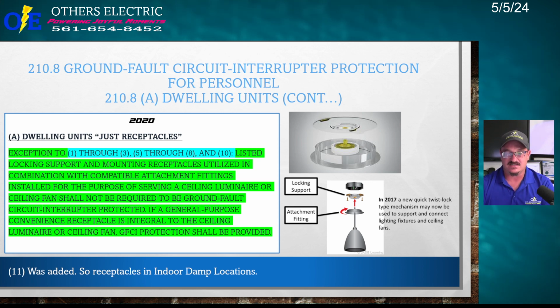if it's for ceiling luminaires. But now I want you to remember, if you're going to put an outlet there, remember you used to have those keyless fixtures with the light in them? You know what I'm saying? The keyless fixtures used to have the plug in them. You used to be able to get them, and it had a light, and you could also plug into a receptacle. If you're going to put one of those in there, it does have to be GFCI protected. All right? So just realize this, that if you're using these receptacles for ceiling lights, because it's basically a receptacle, it's excluded, okay? You're allowed to not put those on GFIs.